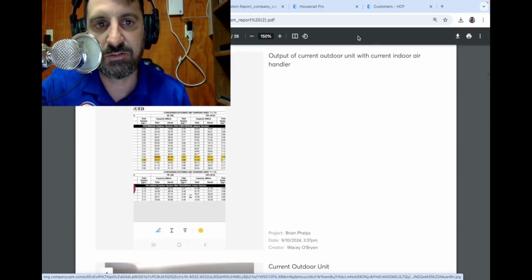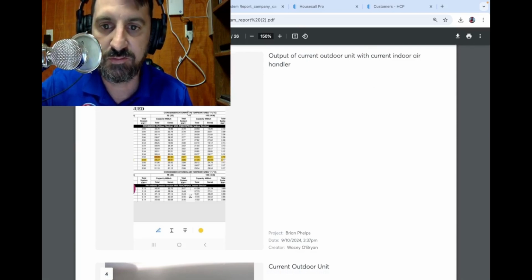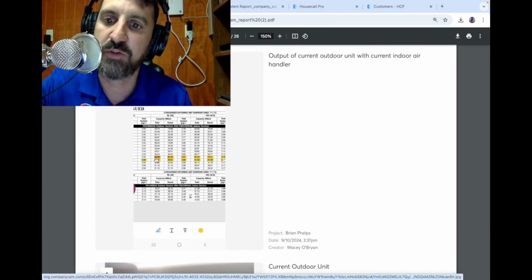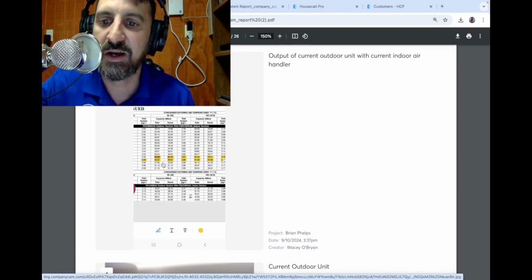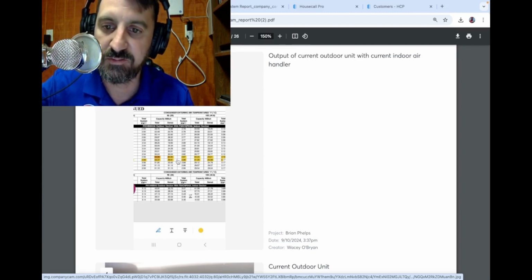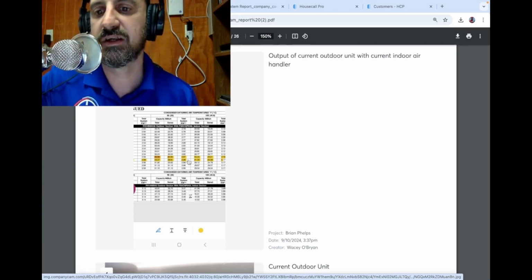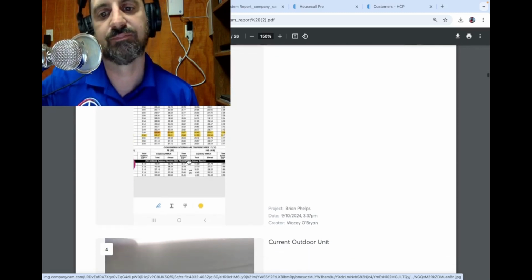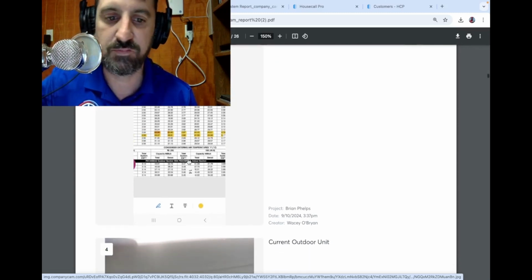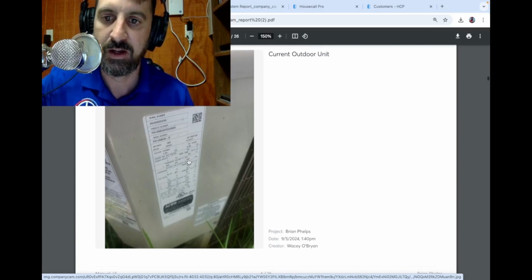And then I went ahead and looked up the output of the current system for them. As you can see, it's running 36, almost 37,000 BTUs at peak. And depending on how the airflow and static pressure is, it can be around 33,000. But basically, either way, we're way oversized on this house already.